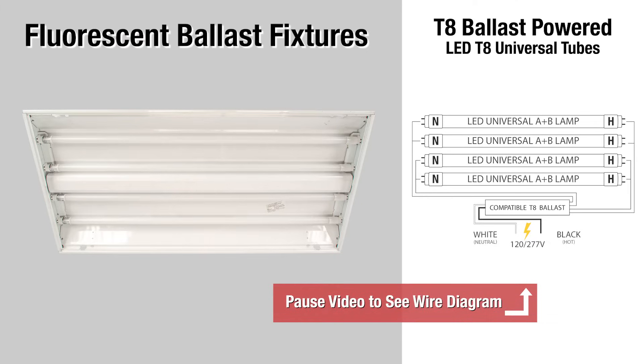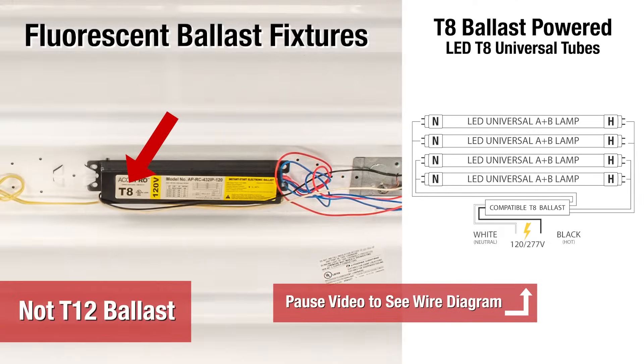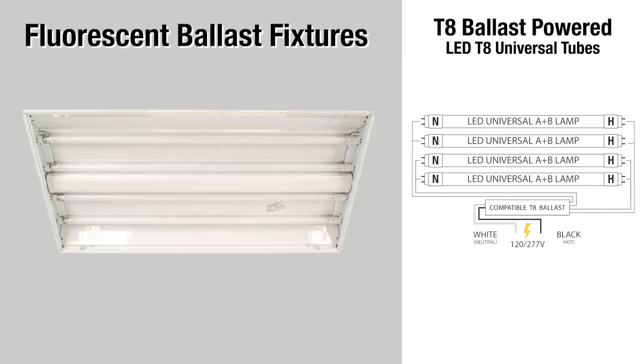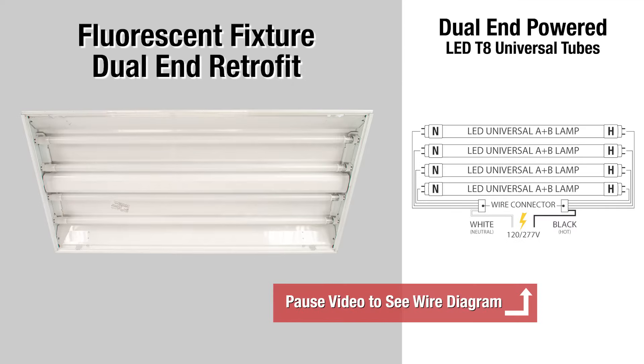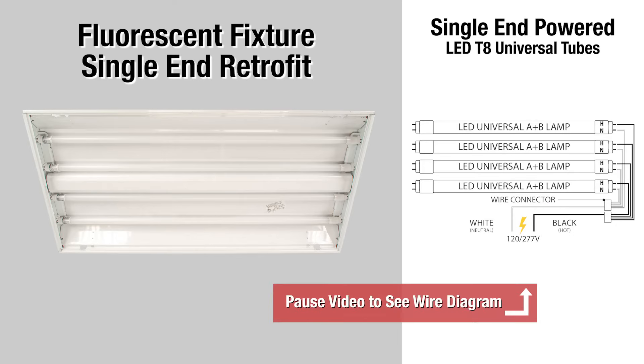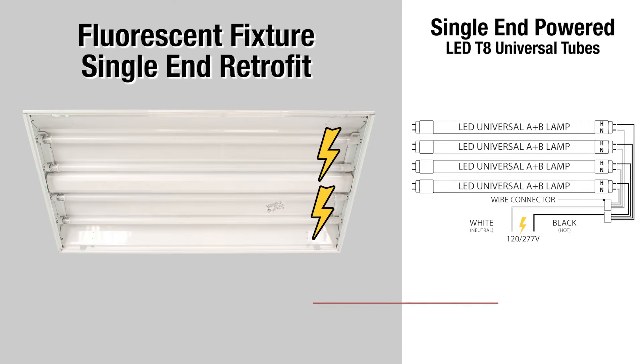It works in fluorescent fixtures that have a T8 — not a T12 — ballast in them, like this one. It works in fluorescent fixtures that have already been converted or set up for dual-end fed type LED tubes, like this one here. It also works in fixtures set up for single-end fed LEDs that use single-end fed bulbs — they've been around since before 2009. Here's an example of one of those.